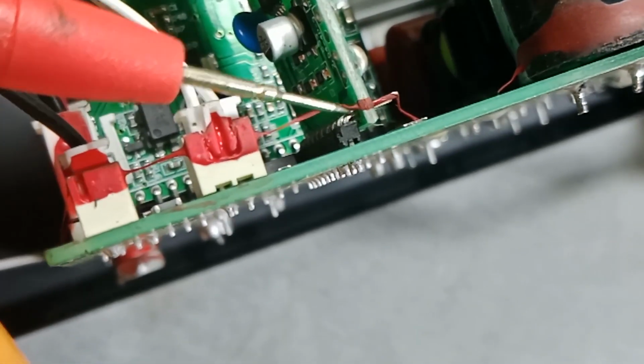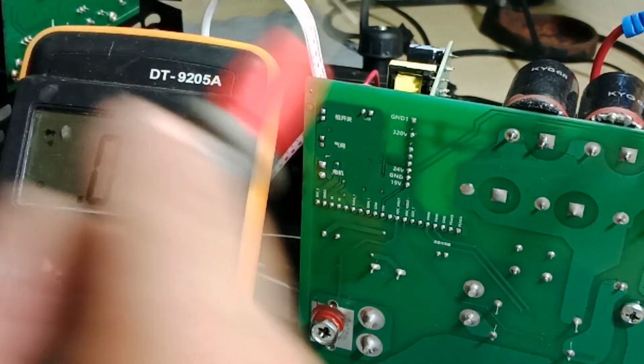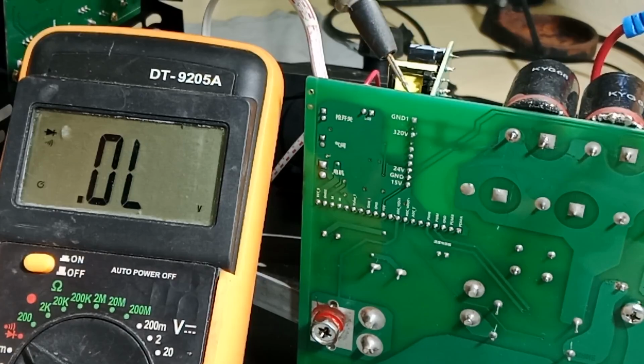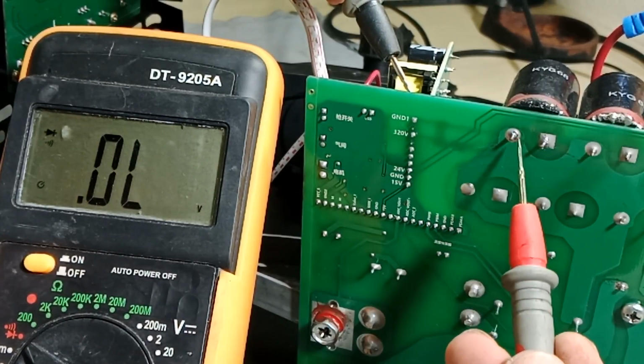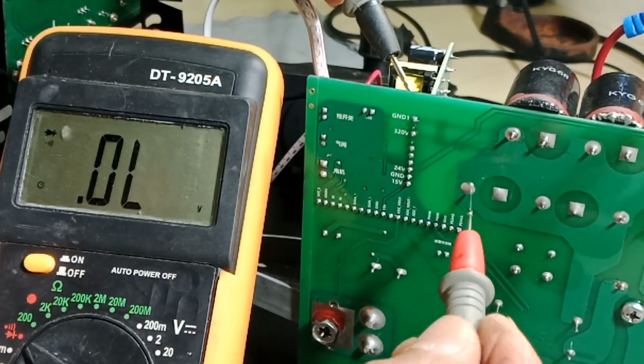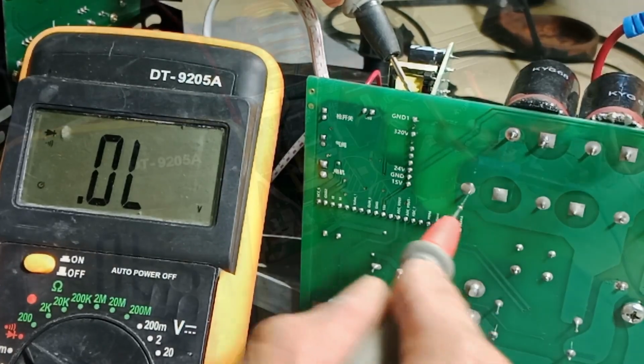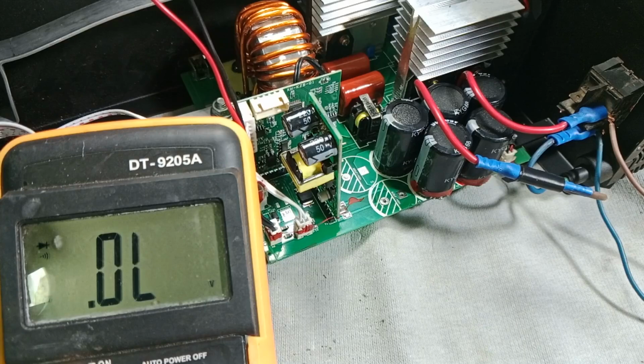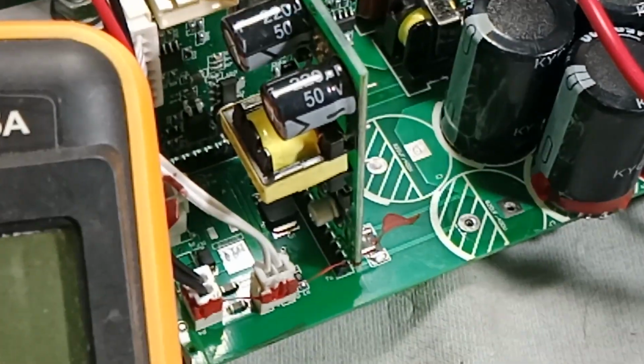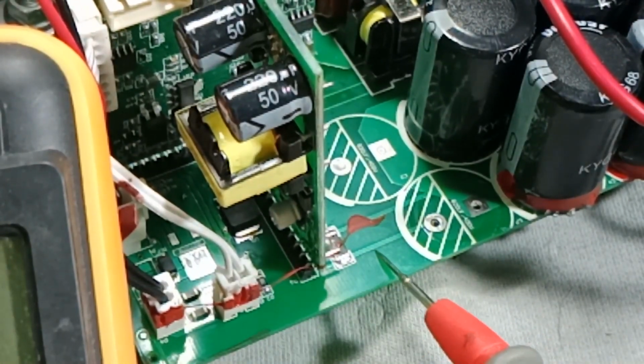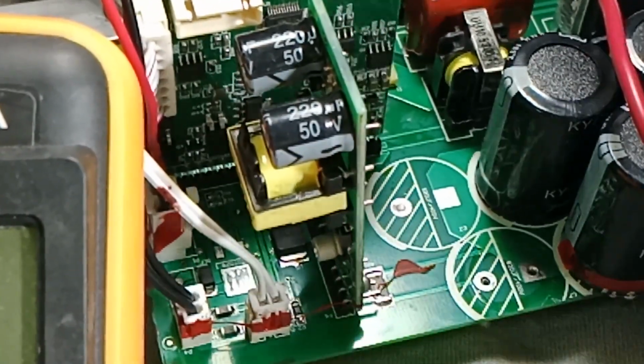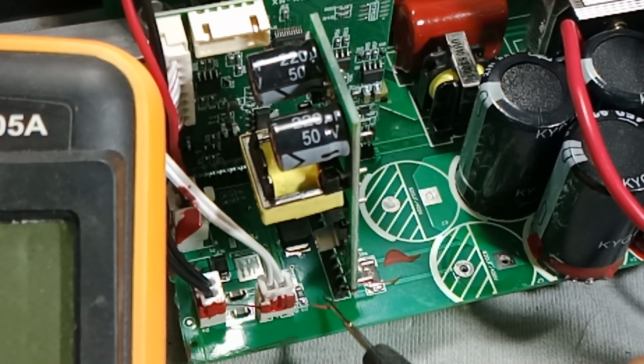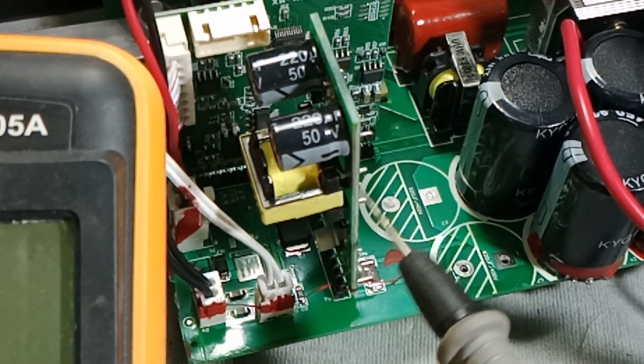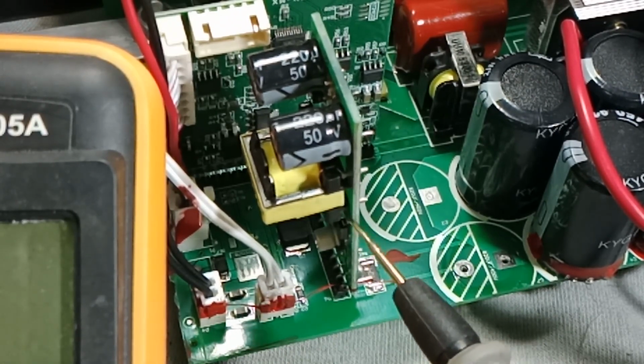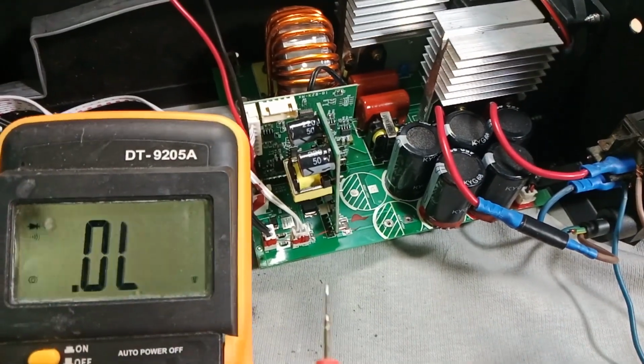The pin of this header should be connected to the 320 volts DC. I am now using the continuity test function of the multimeter and we can see that it is not electrically connected. I temporarily removed this capacitor just to show you the PCB trace that leads to the 320 volts DC. This small PCB is the auxiliary power supply module for this unit. If there is no 320 volts DC going to that board, then the auxiliary power supply will not work, and so is the whole welding machine.